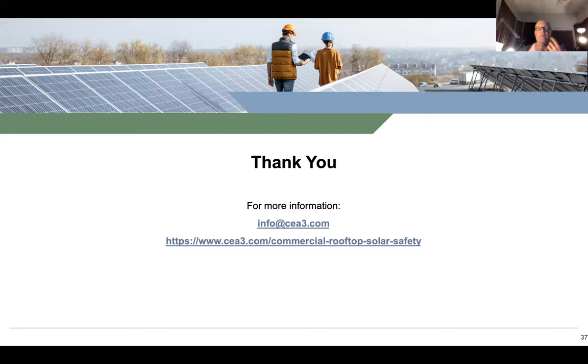Another question asking about infrared scans and the regularity and frequency of those. How often do you recommend infrared scans? The higher the frequency, the better, but typically during a normal operations and maintenance schedule, we recommend that infrared scans are done for the PV modules, at least a sample of the PV modules on your site, and 100% of the enclosures every 6 months.